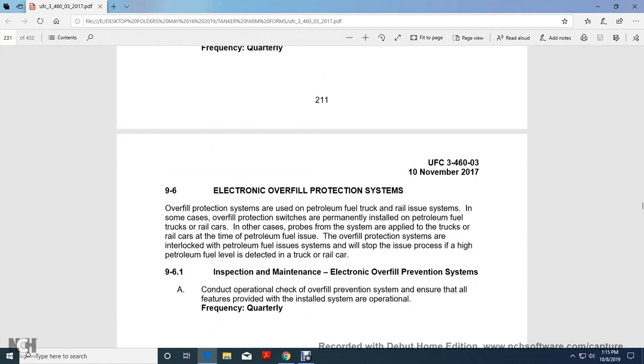Electronic overfill protection. Overfill protection is used with petroleum fuel truck and rail issue systems. In some cases, overfill protection switches are permanently installed on the petroleum fuel trucks and rail cars. Otherwise, probe systems are applied to the trucks and rail cars at the time of petroleum fuel issue. Overfill protections are interlocked with petroleum fuel issue systems and will stop the issue process when a high petroleum fuel level is detected in a truck or rail car.